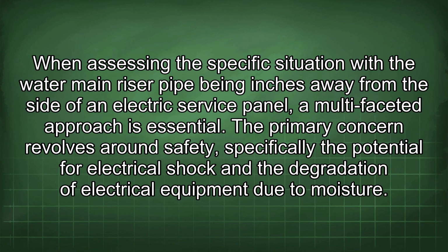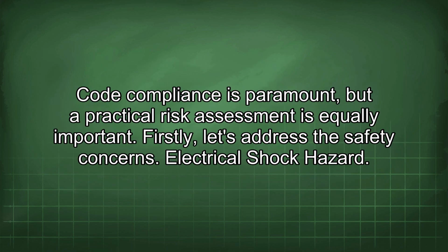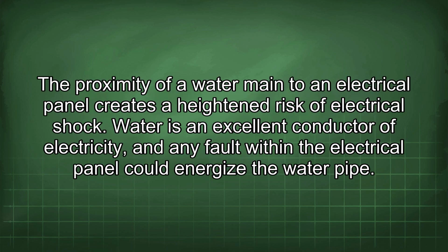The primary concern revolves around safety, specifically the potential for electrical shock and the degradation of electrical equipment due to moisture. Code compliance is paramount, but a practical risk assessment is equally important. Firstly, let's address the safety concerns. Electrical shock hazard. The proximity of a water main to an electrical panel creates a heightened risk of electrical shock.